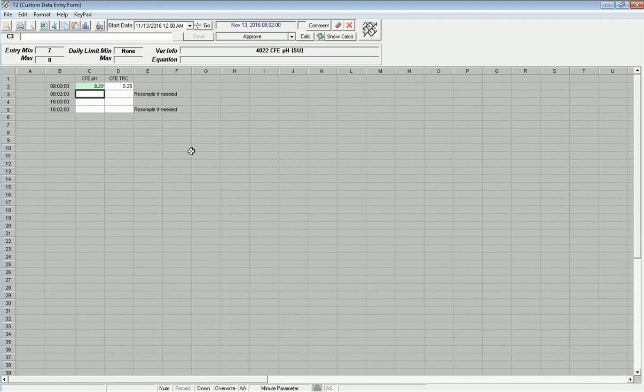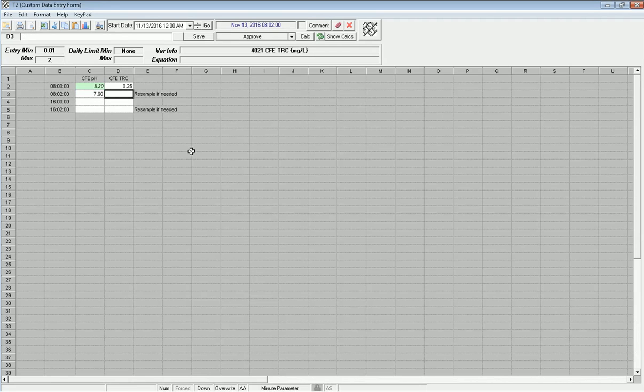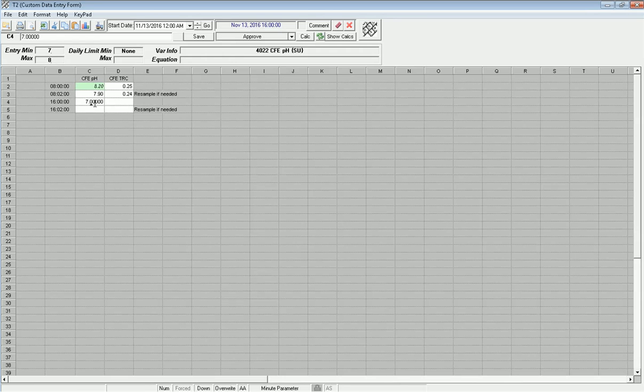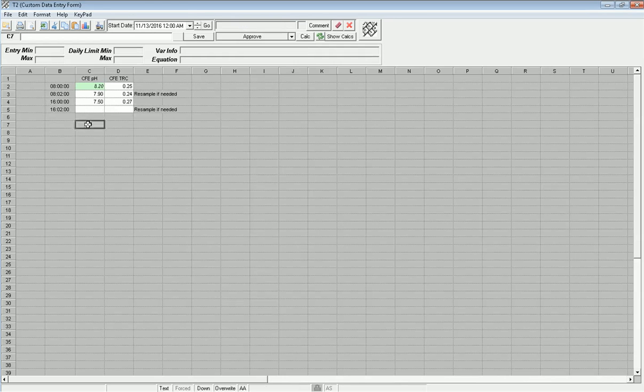And if I go in here now, and I've got to do a resample because of that 8.2, I'd say, OK, now it's 7.9, which is more normal. The associated chlorine residual is 0.24, so it hardly even changed in two minutes. My pH reading is 7.5. My chlorine residual is 0.27. And in this case, I don't need to resample, OK? So I can go ahead and click Save.